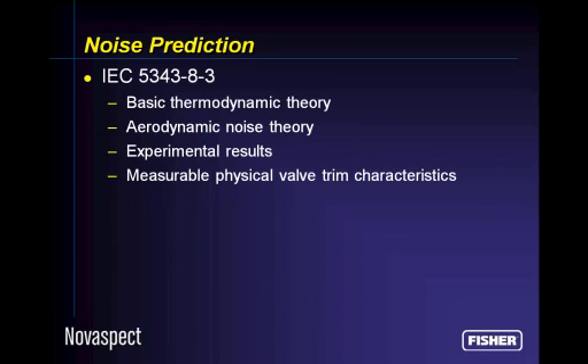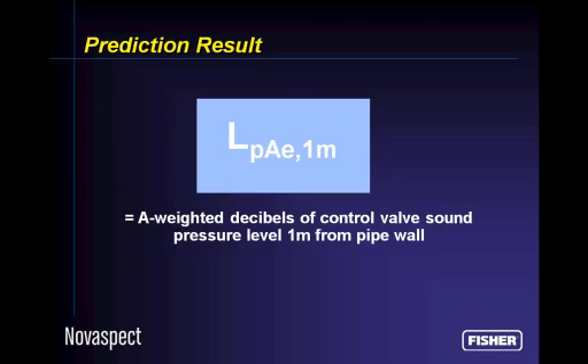We use some basic thermodynamic theory, aerodynamic noise results, some experimental results, and some things that we can measure about the valve physical trim characteristics, and we end up calculating the A-weighted sound pressure level in decibels, as measured 1 meter downstream of the valve and 1 meter away from the pipeline.